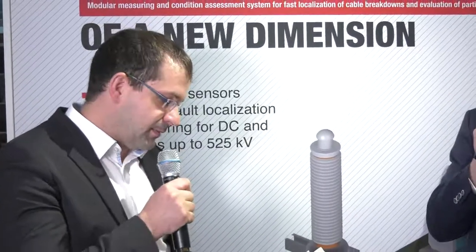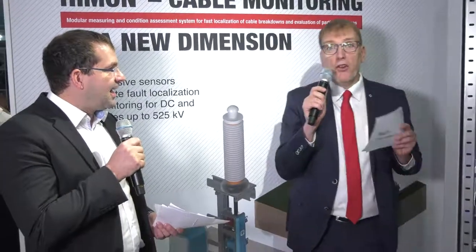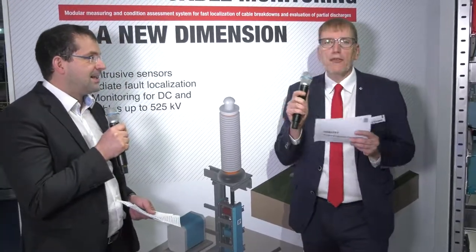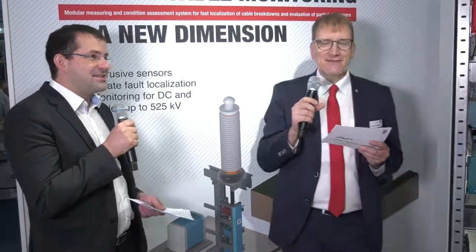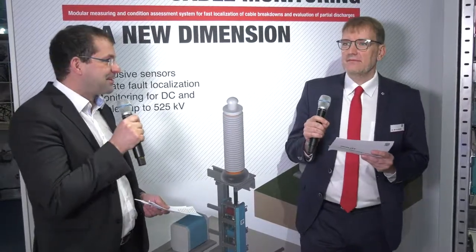cable transition station. Dan, here I have to jump in shortly, because you will find also figures like 5 or 7. The six reactors is dedicated to the average of the typical cable type. So if the cable type changes regarding the capacitance per kilometer, then you might have lower or even a little bit higher. This is a very important hint. Testing power required, so therefore the average will be 6 for the 150 kilometers.